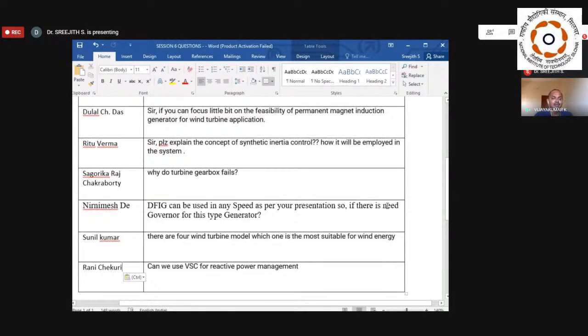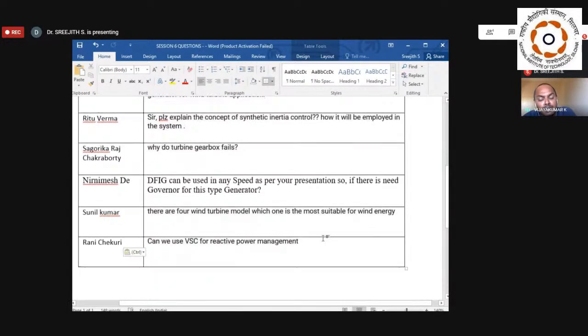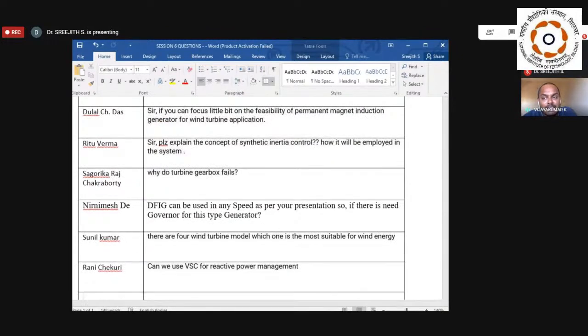The reason is that permanent magnet machines are able to generate power at low speed also. So you can directly connect your generator to the wind turbine without any gearbox. Even for small turbines, in some buildings you may find small wind turbines of 5 kilowatt or 10 kilowatt. In those also they won't use gearboxes. For that purpose we can use the permanent magnet synchronous machine, not a permanent magnet induction. There is no permanent magnet induction generator.